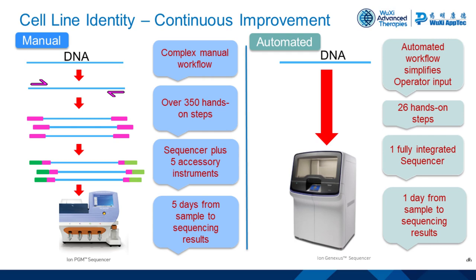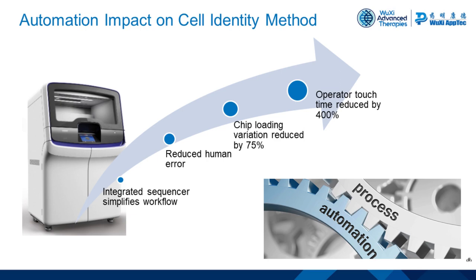While the cell identity test is a robust method, the manual procedure using the PGM involves a complex and time-consuming workflow. Recently, we have improved the method by automating the procedure on the GeneXus integrated sequencer, simplifying the workflow and reducing operator input. Over 350 hands-on steps have been reduced to only 26 steps performed by the operator. The integrated sequencer replaces the PGM plus five other accessory instruments, reducing the lab footprint, instrument maintenance, and service costs. What used to take five days from sample to sequencing results can now be accomplished in one day. Automating the workflow has reduced human error and interoperator variability — for example, variability in loading the sample into the sequencing chip has been reduced by 75%, and operator touch time reduced by 400%.